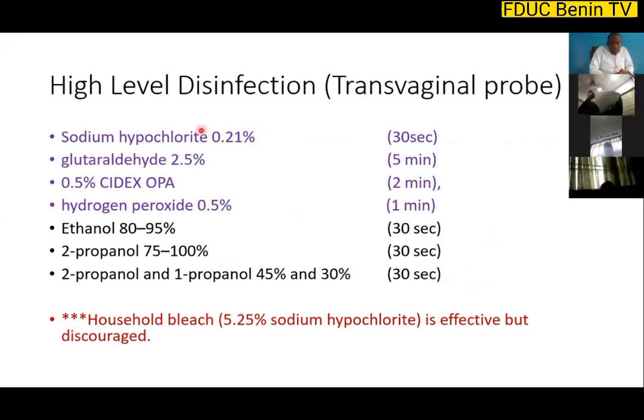And again, these are some of the agents that we can use for high-level disinfection. Glutaraldehyde 2.5% is readily available in Nigeria. The low concentration sodium hypochlorite and hydrogen peroxide are available, and we can get some of these and use them for our transvaginal probe. I must sound a note of caution here. What is very important is that some of these machines, the probes, are sensitive, and you must consult the user manual to know which is the best one. One umbrella does not just fit all.